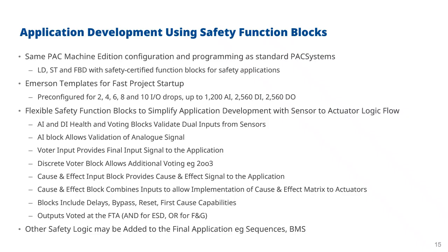As well as the pre-configured templates, we've also included flexible safety function blocks to simplify the application development and to control all of the flow of logic from the sensor to the actuator. So first of all, there are analog input and digital input health and voting blocks. They validate the dual inputs from the sensors. There's an AI block that allows validation of the analog signal. There's voter inputs, which can give that final input signal to the application.